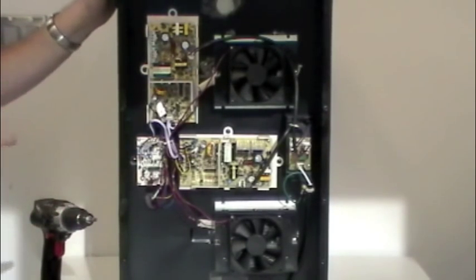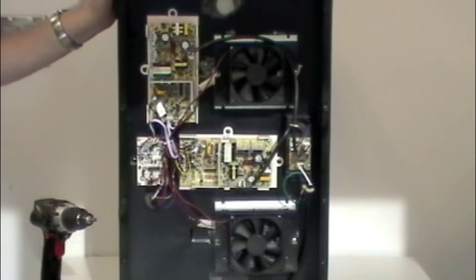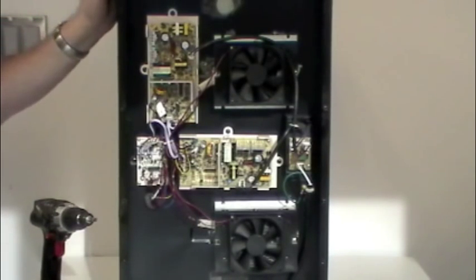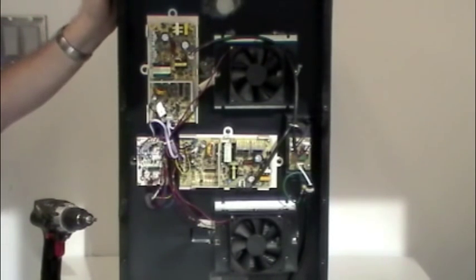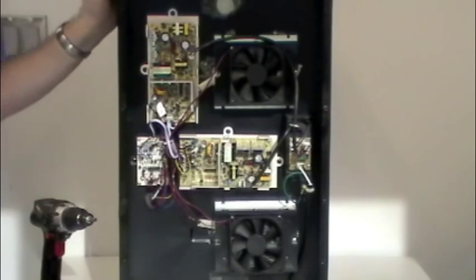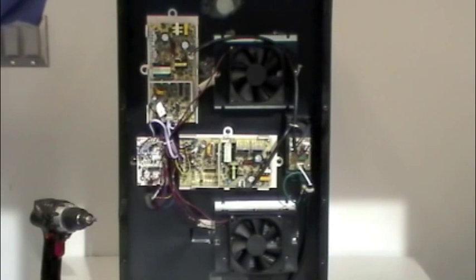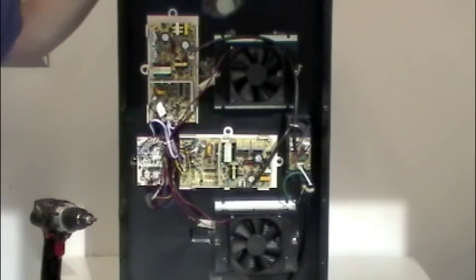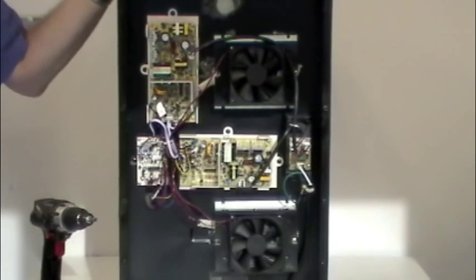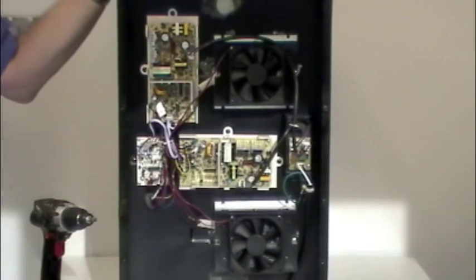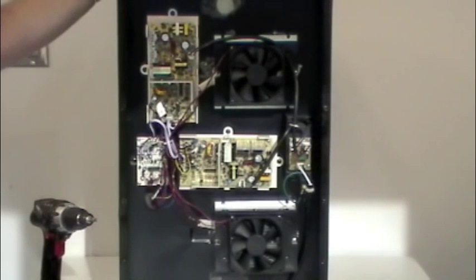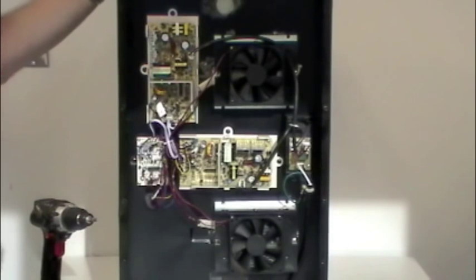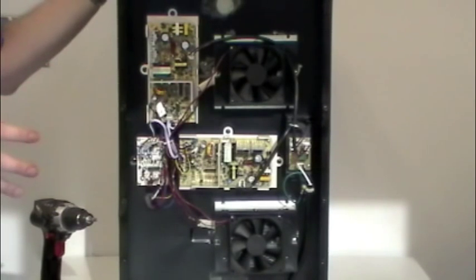These boards are just replaced as a single module. You would call customer service, order the board. The board comes in. You put the screws in and attach them to the back of the unit and plug everything into it. And that's really all that you need to do. And then you would power the unit up. Make sure it's cooling. Make sure there are LED lights. Red, solid all the time. And green. Let me get into that for a minute. On these LED lights, that red light that indicates that power is applied to the board, that one's going to stay on all the time. The green one that indicates node activation is dependent upon the thermostat setting that we have it at. So we're going to see an occasional cycle. We'll see a period where that green light is off and then it comes back on. And then it goes off again. And then it comes back on. So we should get an occasional pulse out of it. The red light should stay constantly on all the time.